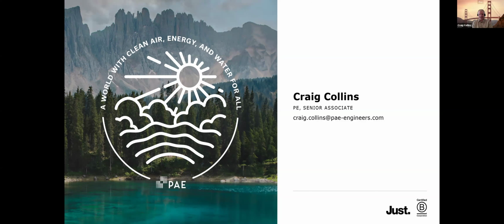We've had quite a few clients now request assistance for designing UPSs into their projects, mostly for low to mid-rise applications. There's a lot of interest in urban environments where there's not much room for generators, or concern about providing space for the generator indoors. If there's not room for the generator on the exterior of a building, the space premium for generators can be quite high. So UPS might be more expensive on equipment cost, but you can get quite compact UPS systems now with lithium ion technology. There are a bunch of fire safety concerns associated with lithium ion batteries as well. So I'd just say it's good to consult your architect, your MEP design team, and your elevator vendors. If you're planning a UPS-backed elevator, it takes really tight coordination between all parties.